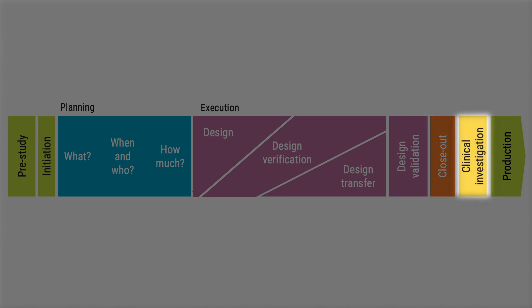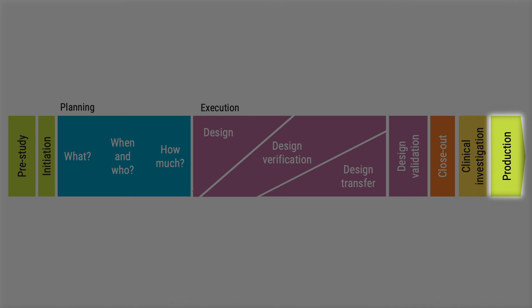When done, you can CE mark the device or proceed to a clinical investigation and then CE mark the device. If you're aiming for the US market, you would seek FDA clearance or approval through a pre-market notification or pre-market approval process. Even after the project ends and the production department has taken over, you should still be working with design control — using change control on any changes you need to make, and updating your risk management file, clinical evaluation report, and other relevant documents as you learn from your product on the market.